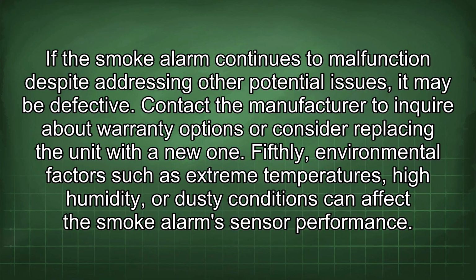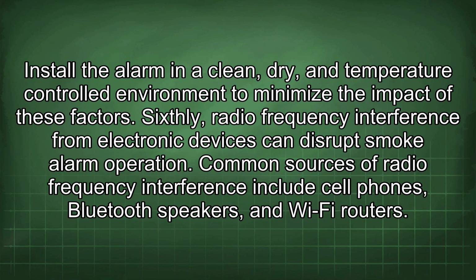Fifthly, environmental factors such as extreme temperatures, high humidity, or dusty conditions can affect the smoke alarm sensor performance. Install the alarm in a clean, dry, and temperature-controlled environment to minimize the impact of these factors.